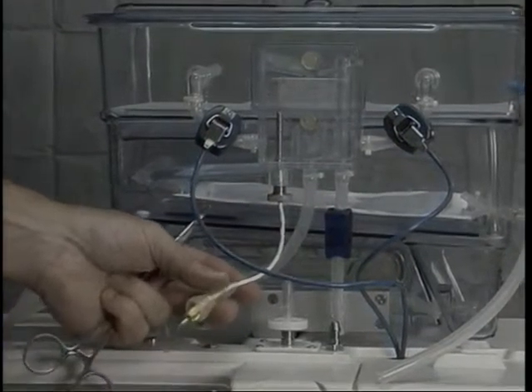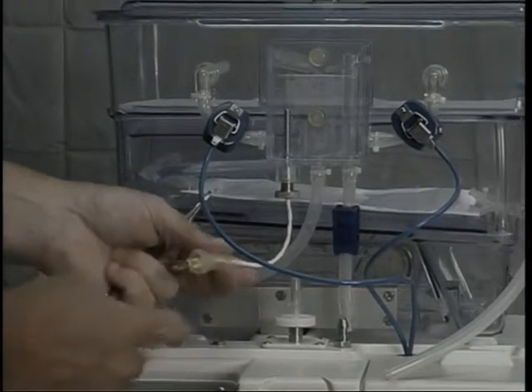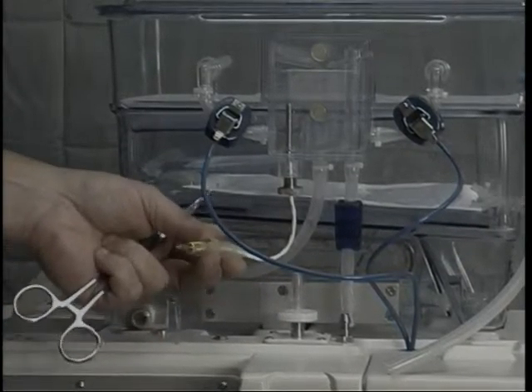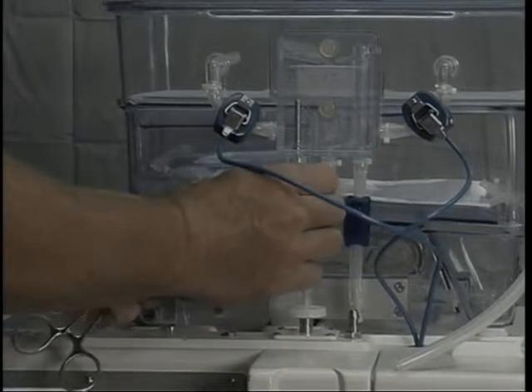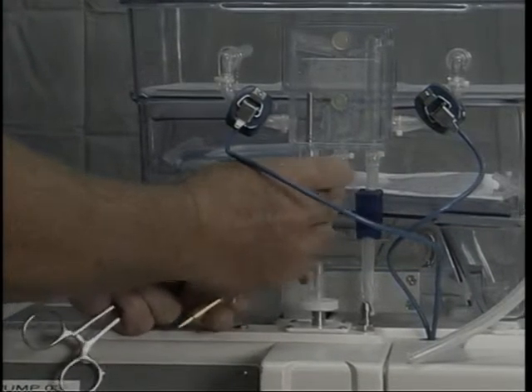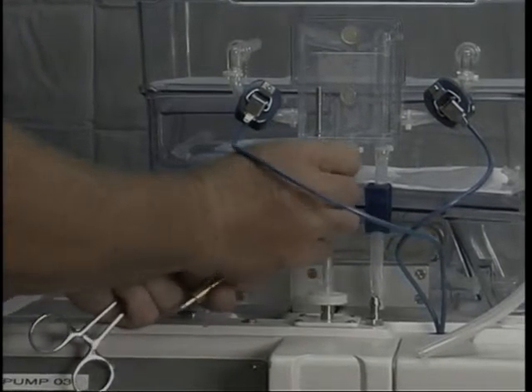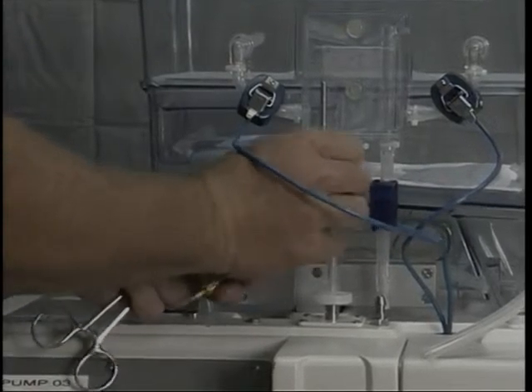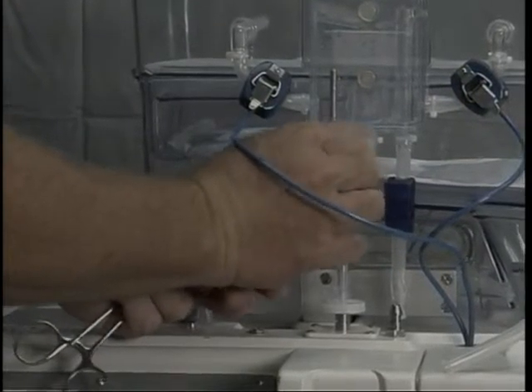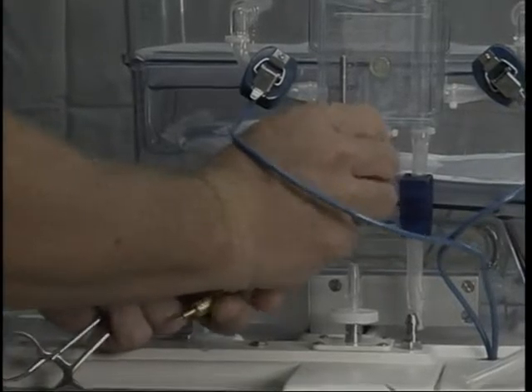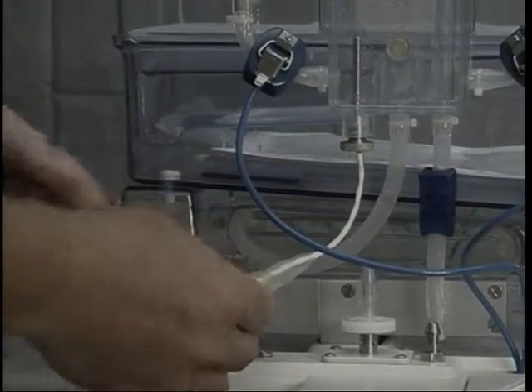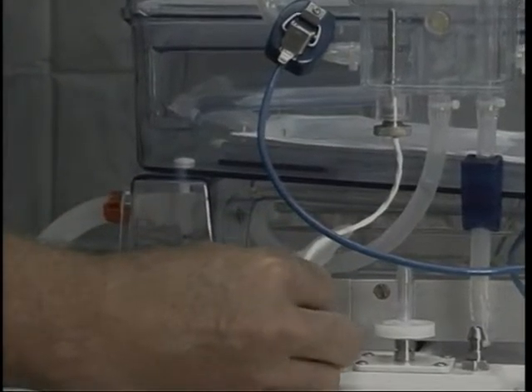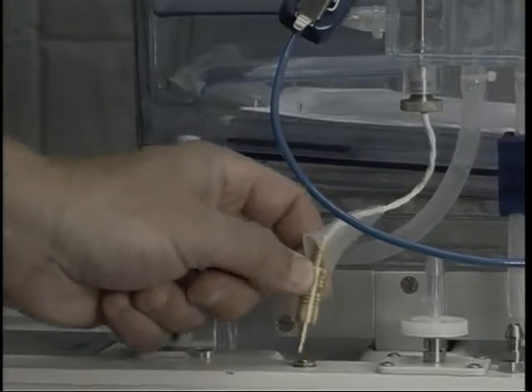Now you're seeing the technician place the temperature probe into the cassette. It is important to note that you place the temp probe into the cassette only hand tight prior to placing the probe into the machine. This prevents the technician from damaging the temp probe.